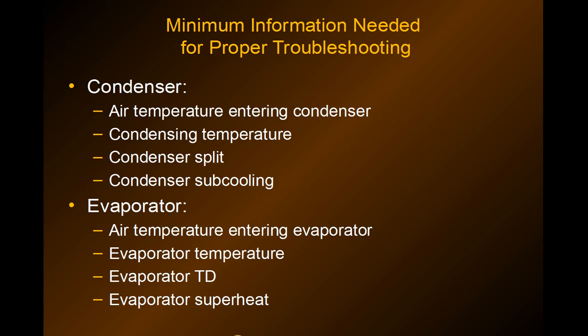For the evaporator, you need the air temperature entering the evaporator, the evaporator temperature, and the evaporator TD — which is the temperature differential. Remember that's different than the evaporator split. You also need to know what the superheat of the evaporator is supposed to be.